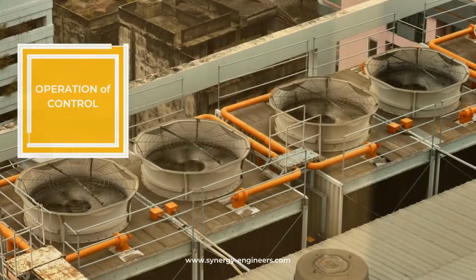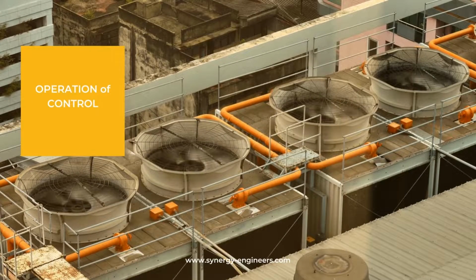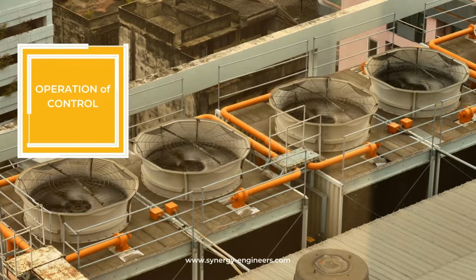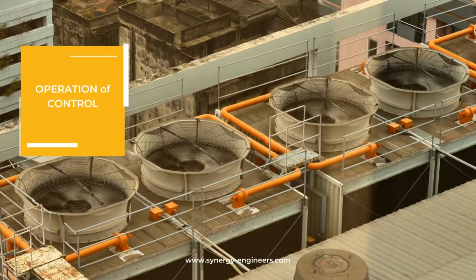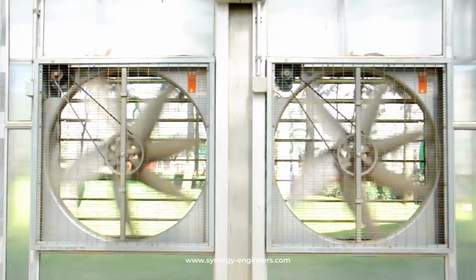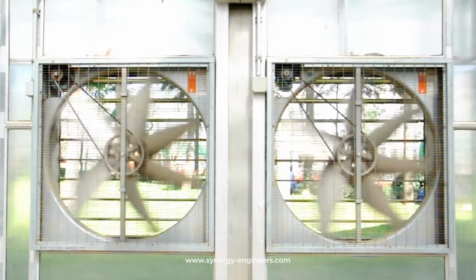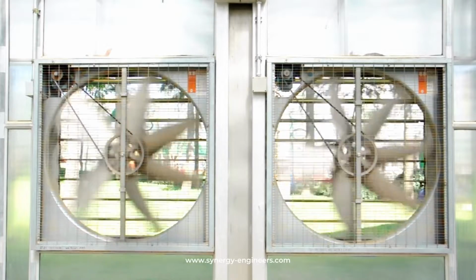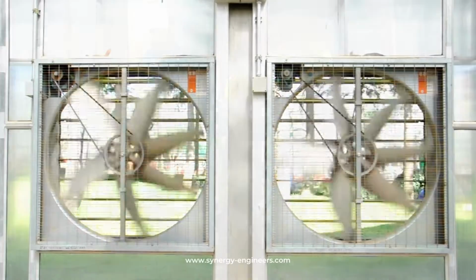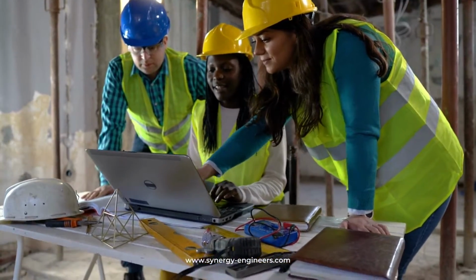The third thing we look at is the operation and control. Typically, in the industry now, we have variable air volume systems, so that single fan is controlled by a VFD, and that fan is either sped up or slowed down to match the load and airflow requirements downstream of the air handling unit.